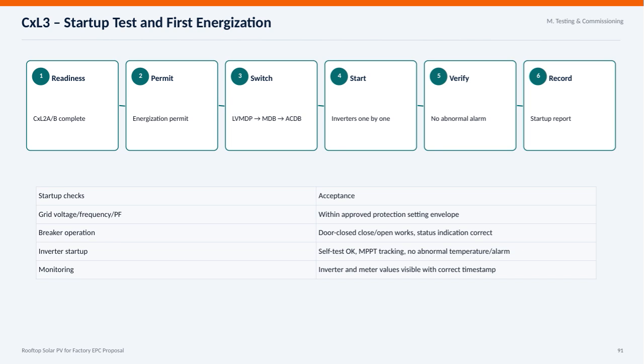Key acceptance criteria include grid voltage, frequency, and power factor within the approved protection settings, proper breaker operation with door closed status indications, successful inverter self-tests and MPPT tracking, and accurate monitoring data with correct timestamps. This thorough process guarantees a safe and efficient system commissioning.